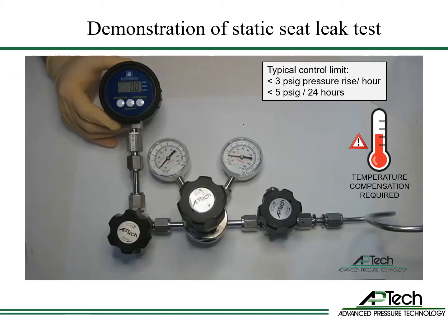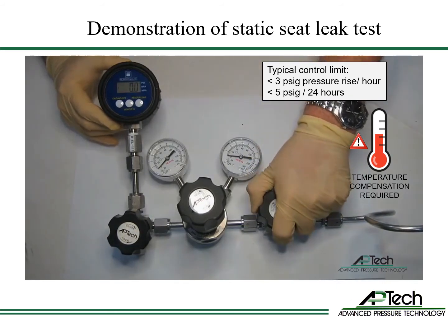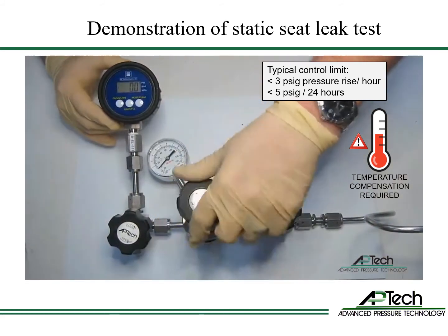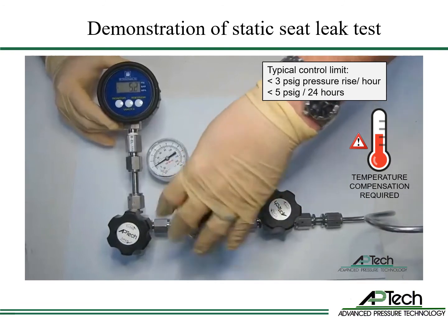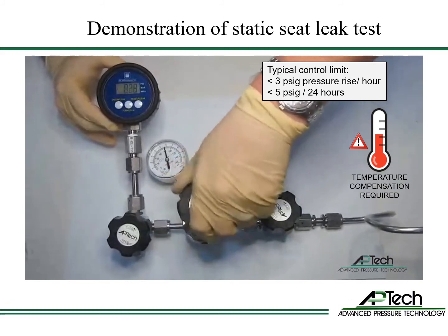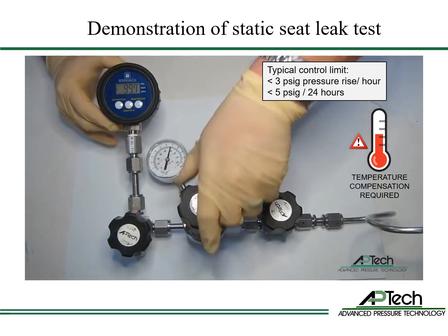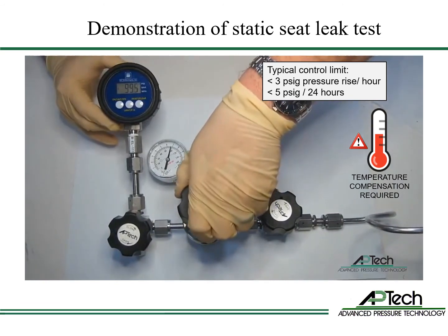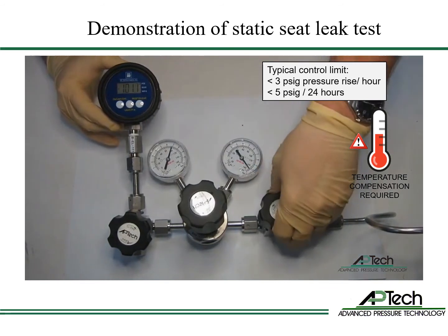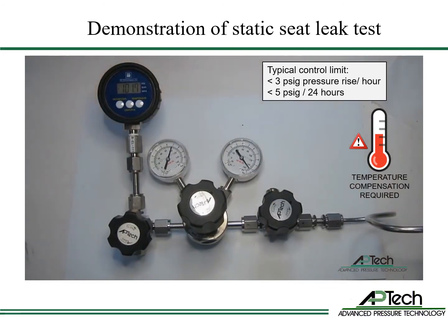Now let's demonstrate the static seat leak test for a regulator. Begin by pressurizing the regulator inlet with nitrogen and trap pressure by closing the inlet and outlet valves. Then set the desired regulator outlet pressure, making sure there is a pressure difference from inlet to outlet. After pressure adjustment, turn the regulator knob counterclockwise a quarter turn to release adjustment range spring force on the diaphragm. Confirm the shutoff of the upstream valve and downstream valve and monitor for a pressure change — rise or drop. An outlet pressure rise is an across-the-seat leak. Pressure drop is an outboard leak. Typical test specification is not more than 3 psig pressure rise in one hour and/or 5 psig in 24 hours.